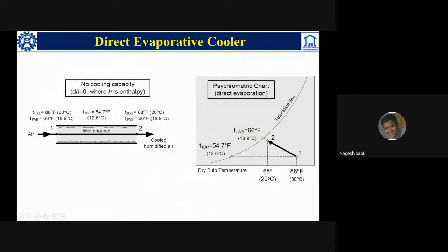If you want to look at what is happening in an evaporative cooler through a psychrometric diagram, air enters through a wet channel, as I have shown in the wet medium. It cools adiabatically, so it tries to move towards the saturation line. So there is cooling happening, as I have told you. If we are moving in the left direction in the psychrometric chart, cooling is happening.